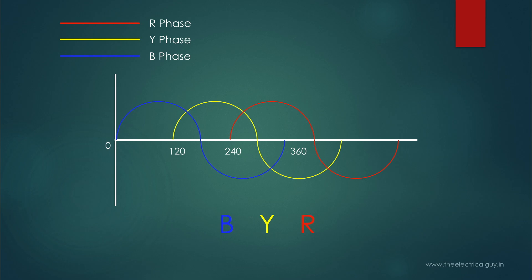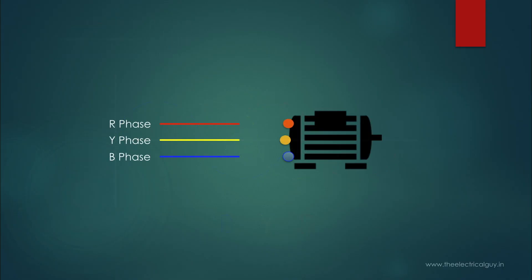Of course, changing the direction of rotation of the magnet is not an option for the end user. You can change the phase sequence at your end also, and that is by interchanging the phase conductors. So for example, this is your three-phase load - let's say an induction motor. If you connect your respective phases in their respective slots, the phase sequence would be R, Y, B. If you want to change the phase sequence, just interchange any of the phases and the phase sequence would also change.